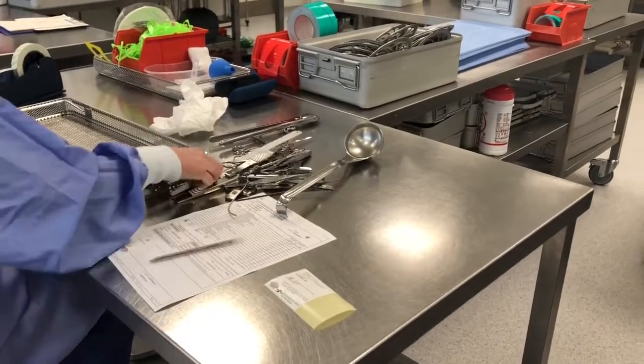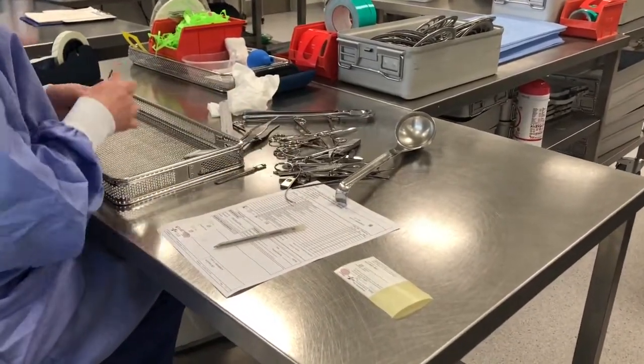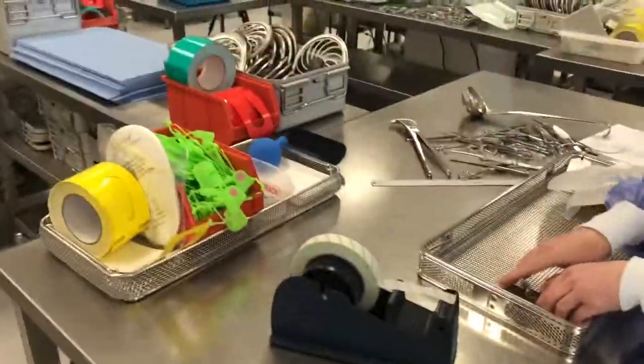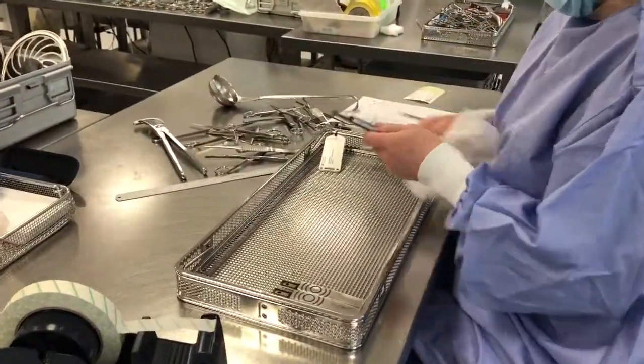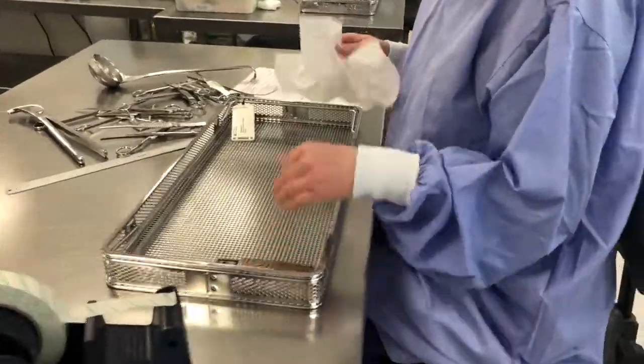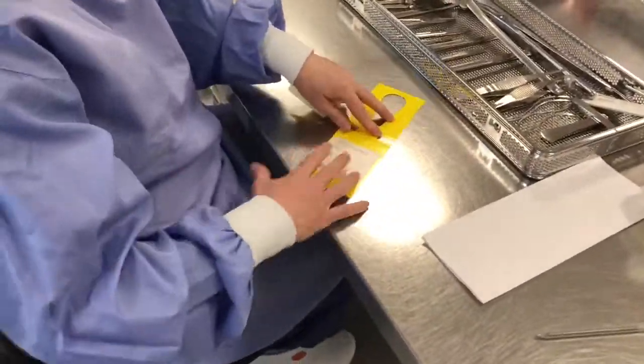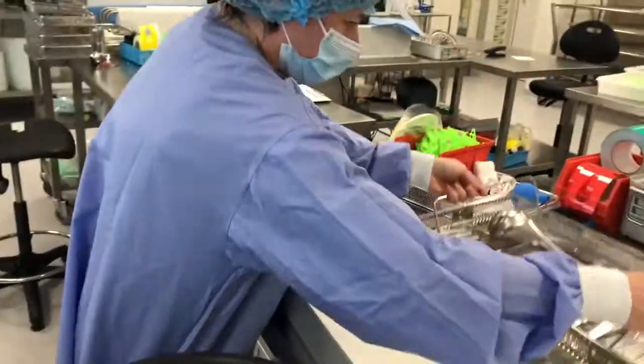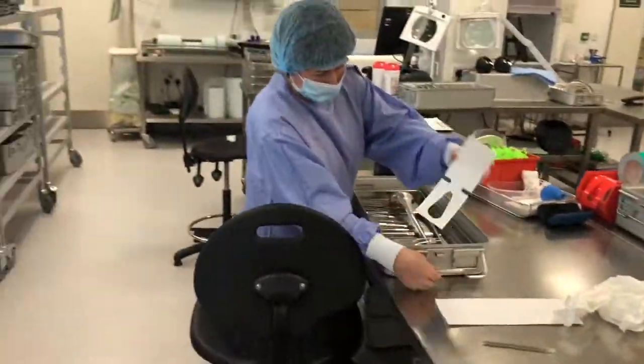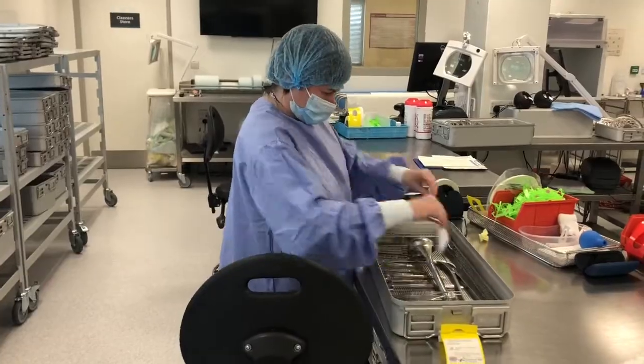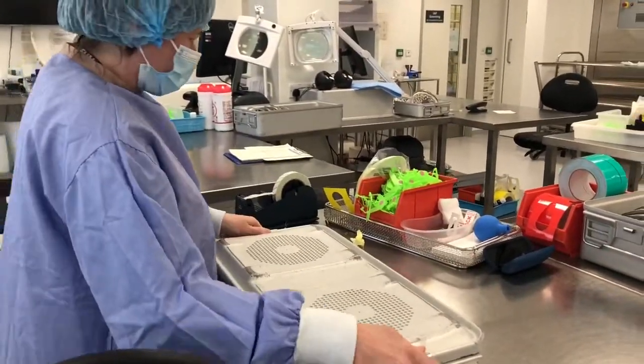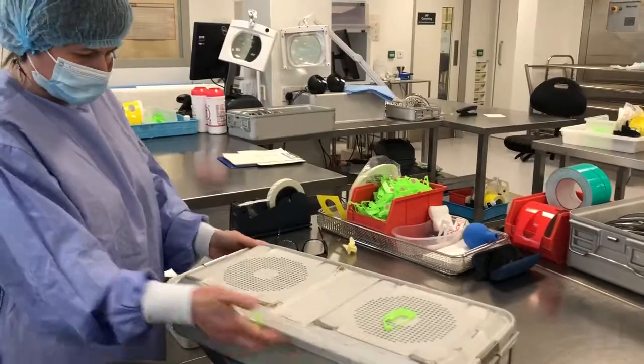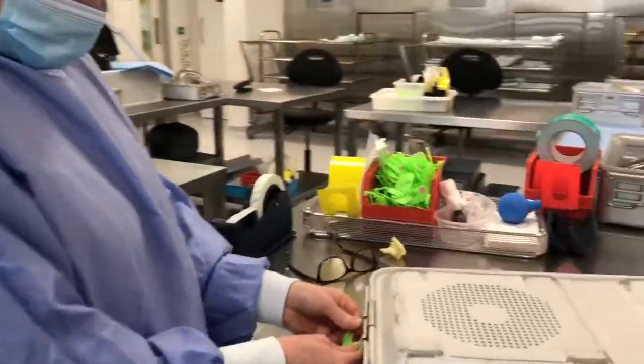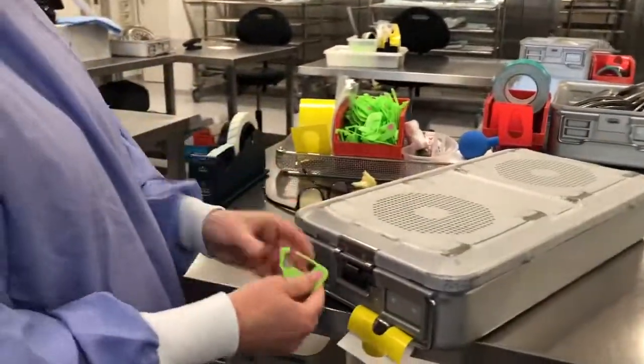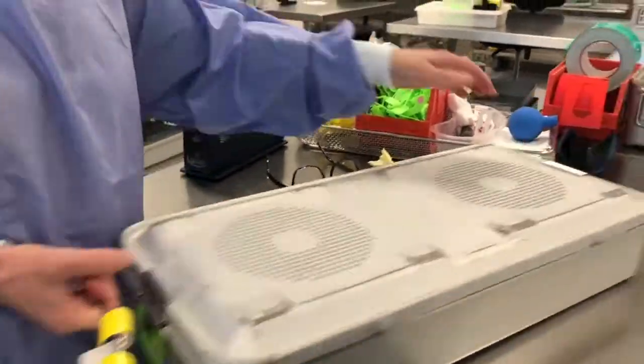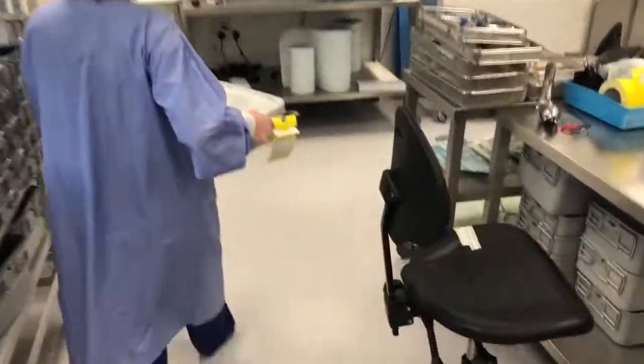The equipment undergoes inspection and functionality testing. This means that each instrument is inspected for cleanliness and to check that it is fit for purpose. Staff are mindful that these instruments are being used on patients and they must be safe to do so. Following inspections and function testing, the equipment is laid out in the trays, left to right according to the checklist. The checklist is ticked by the team member acknowledging what is present in the sets. The set is then placed in a clean tin, again the integrity of which is checked by staff. Each tin is sealed with a lid that locks into place and tamper-proof seals are secured to the tin.